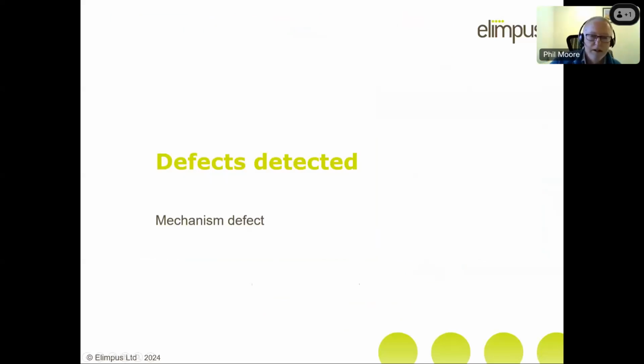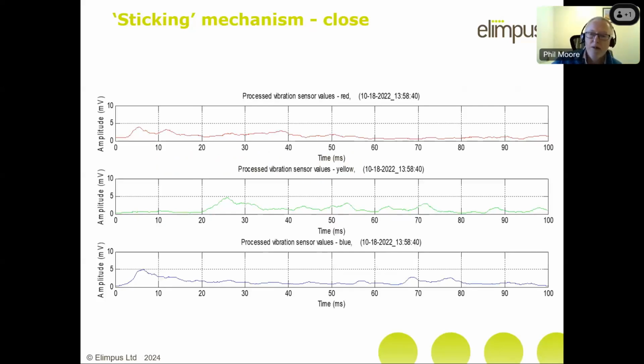I'm running out of time, so let me just quickly finish off a couple more. This is to do with the mech. This was actually a close operation. With close, you don't get quite so much vibration signal here, so the close operation occurred at 0, and you can see here there's a little delay, then the red mech starts to move, the blue one a little bit before it, but you can see here the yellow or the green trace.